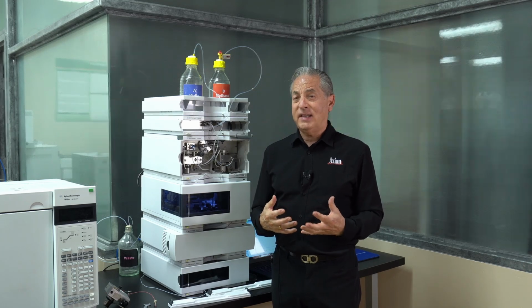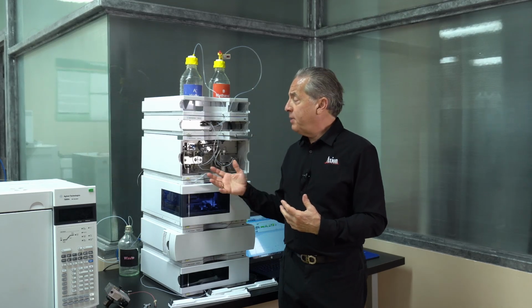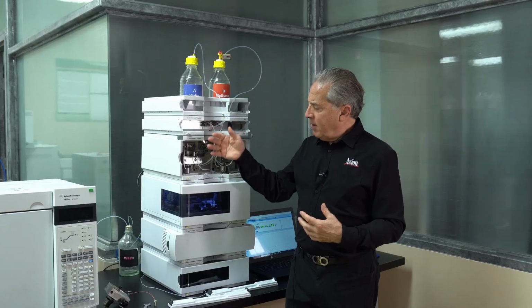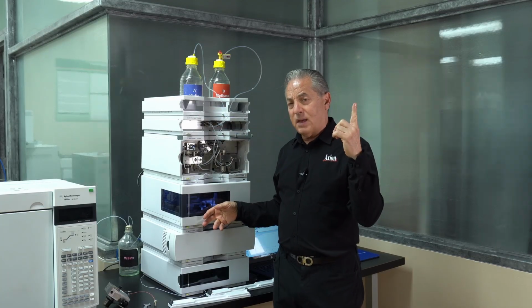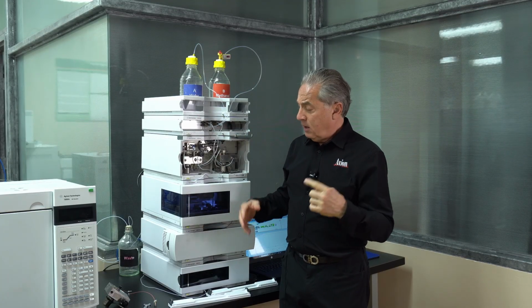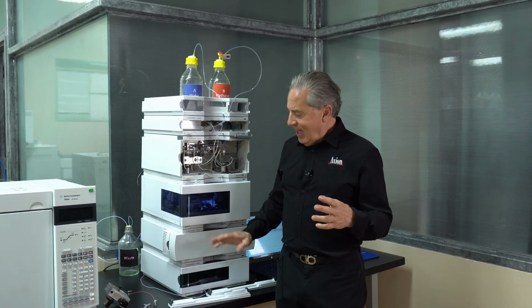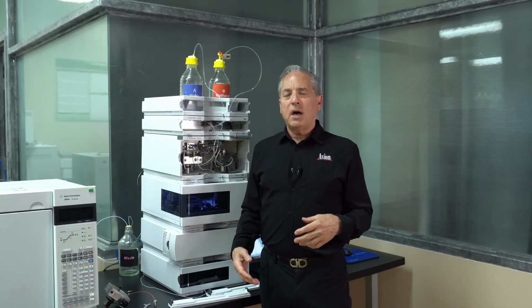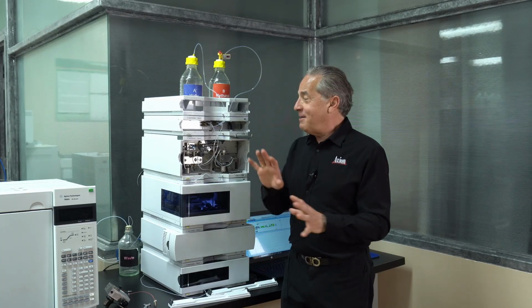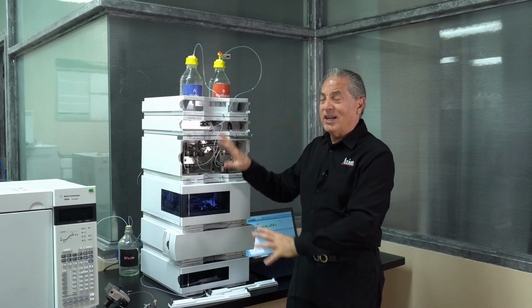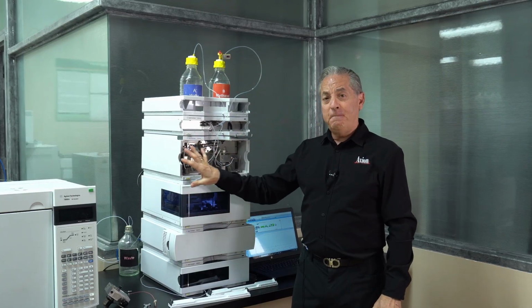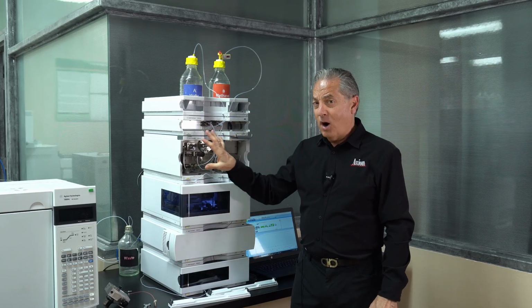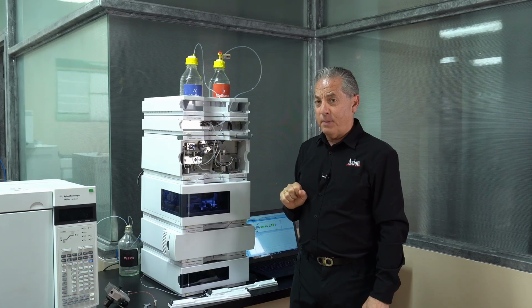So again, I say 85% of all that maintenance is on your pump. The top half should require no maintenance. Your autosampler has one piece that you're going to replace someday. It's called the rotor seal. The column compartment should never go bad. And your detector, when the light bulb burns out, we replace the light bulb. So you get the idea that maintenance is pretty logical every place. But the major part of it is going to be inside the pump itself.